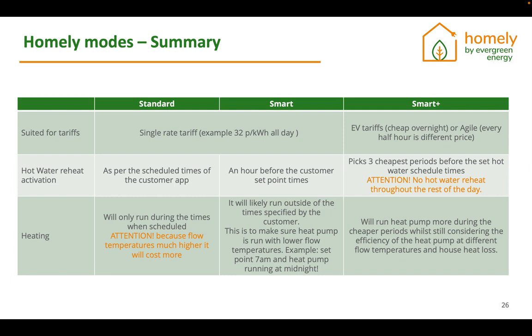And the last is Smart Plus. As mentioned before, it's suitable for the EV tariffs like the cheap overnight or agile tariff. In terms of the hot water reheat, it will pick the cheapest 3 periods before the set times for the hot water. So it'll try to utilize those cheap electricity pockets. And for the rest of the day, the hot water reheat is actually going to be turned off. So if the customers have more than expected hot water demand during the day, they would need to use the hot water boost to heat their hot water tank with electricity that might not actually be the cheapest.